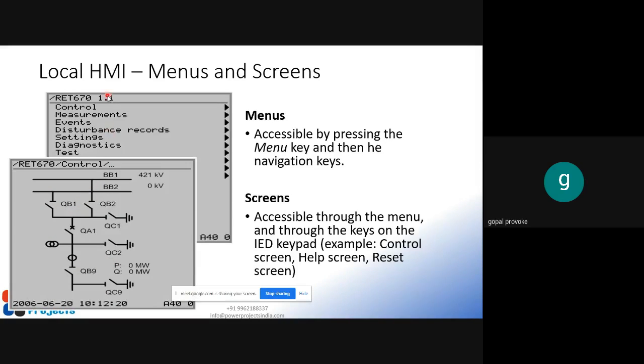And we have measurements, events, and disturbance records. Normal operations like opening and closing are recorded as events, while faults like overcurrent operation or differential protection operations are recorded as disturbances. Whenever there is a fault, this relay will record it as a disturbance.